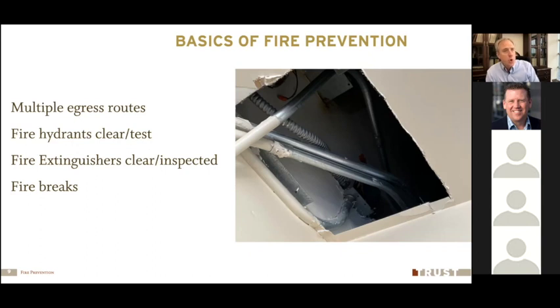We need to make sure those holes get closed back up when we're done with that repair work, because that ceiling panel provides an important fire break against fire spreading should we have a fire in that area. We also need to make sure that we have appropriate fire exits, routes of egress for our employees. There should be at least 2 ways out for employees if they need to evacuate the building in an emergency.